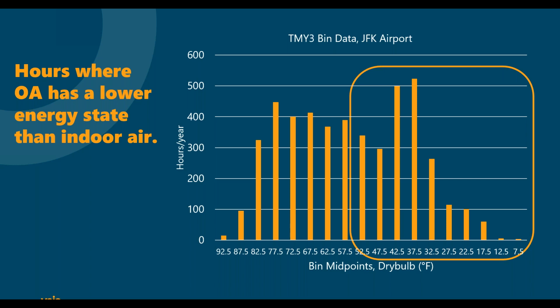I think one of the measures that was called out on a previous slide was a change of use of space. Many times we see that there are spaces that are receiving 100% outdoor air because of a change of use, or a building was reconfigured, and that space doesn't actually need 100% outdoor air. The customer might be thinking, well, that's the equipment that's in place, it doesn't matter, I'll continue to use that because I can. Bringing visibility to how expensive conditioning that virgin air 100% is, as opposed to reusing some of that air you've already paid to condition, that's a great slide and a great way to engage your customer in talking about what that ventilation strategy could be.